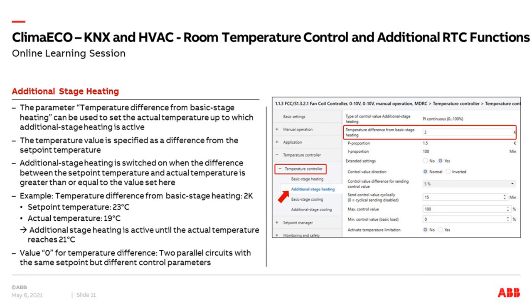For the additional stage heating detail: when to start it — we define a temperature difference between the set point and the actual temperature in the room. For example, if the set point is 23 degrees and the room temperature is below 21, that's a difference of 2 Kelvin and is the starting point for the additional stage heating. The gap is too high, so we start additional heaters. The gap between set point and room temperature will then be resolved very fast. For heating, more than 2 Kelvin difference is the starting point; once you reach less than 2 Kelvin again, the additional stage heating stops.